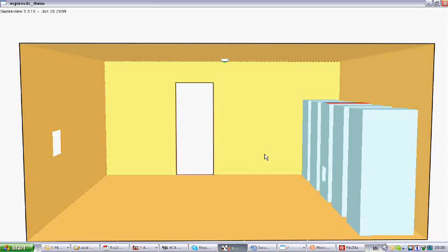So here we have a relatively simple FDS model of a small computer room. The computer room has a door at the far end and 5 cabinets along one wall. In the opposite wall there is a small fan which will be triggered by a VESDA system which we will be installing over the top of the 5 cabinets. A point detector is included on the ceiling which has an alarm threshold of 5% obscuration per meter and no delays.